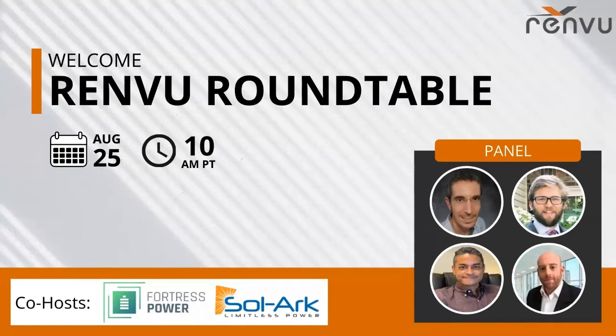Sure, I see Paul's question: are you planning on making the 5K Sol-Ark able to stack with the 12K? The 5K and 8K inverters are standalone systems, not stackable. If you want to stack systems for more power, you'd go with the 12K inverter. You can stack up to 8 of the 12Ks in a 120/240 volt configuration, and up to 9 for 120/208 three-phase configurations.